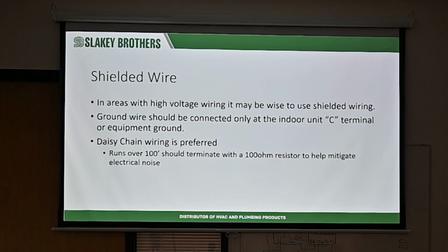The ground on that shield only connects to the C of the indoor unit, or the C on the outdoor unit if you're using it for the outdoor. Don't connect it at both points. There's no C terminal on the Connex controller anyways, so if you're using it with the Connex, you don't have to worry about that, but don't connect it to the outside, only connect it to the inside.